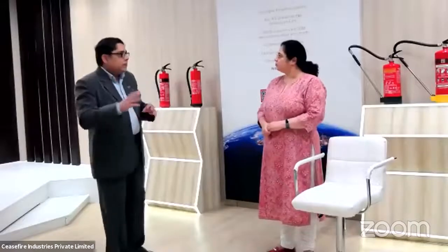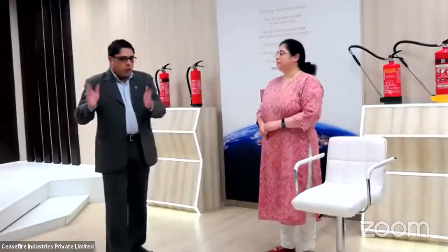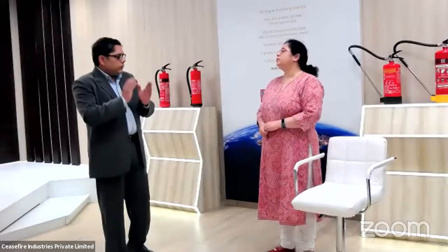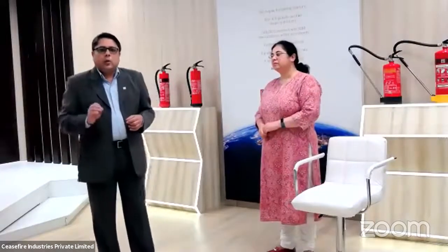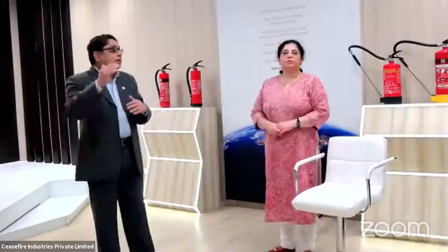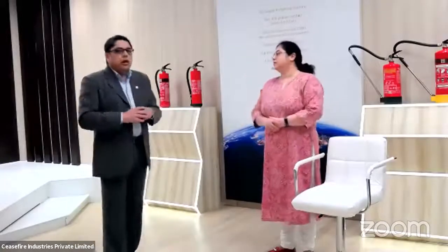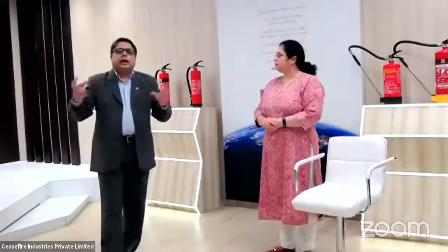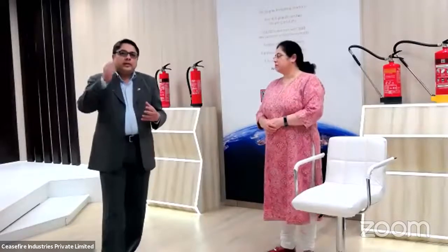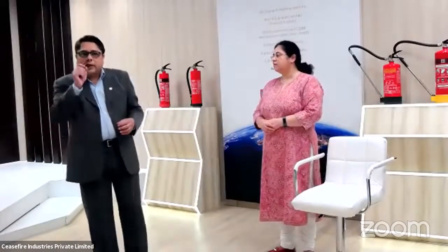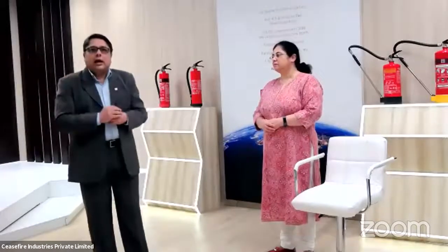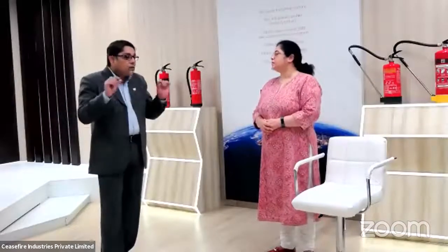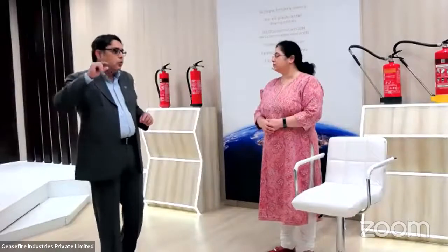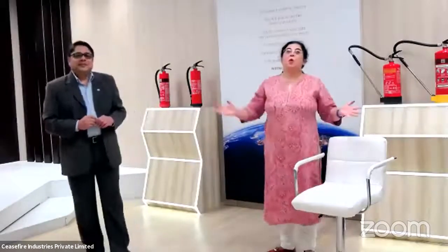It is a tube which has been checked by LPS 1666, a standard to which the low pressure system conforms. But this tube works in two distinct ways. One is precise temperature detection, where the flame actually touches the tube and the tube creates a puncture at that spot. The other is where you do not have a flame touching it, but your ambient temperature is rising quite rapidly. Now you can imagine that you have a very rigid tube, and this rigid tube will soften as the temperature rises. The tube is able to detect the weakest spot, the heat concentration on the tube, and that is where it is going to burst. So again, it works like a rate of rise detector. So the tube is the heart of the system, and it is what makes this system so efficient and simple, because we really do not need too many components for the system.